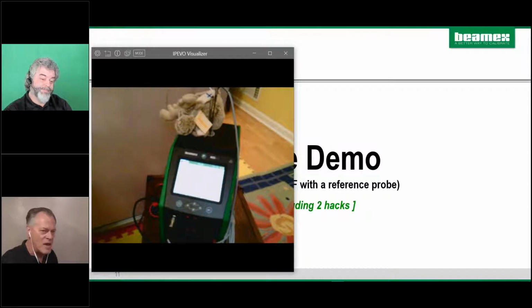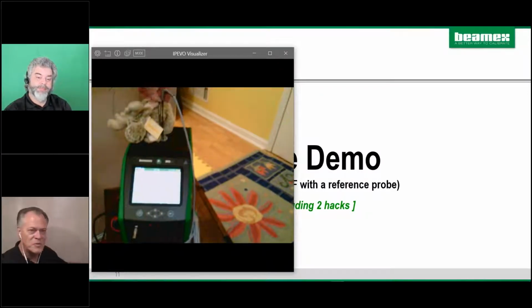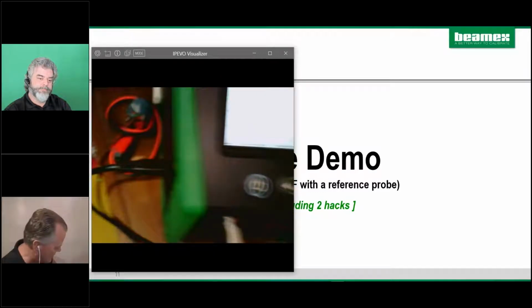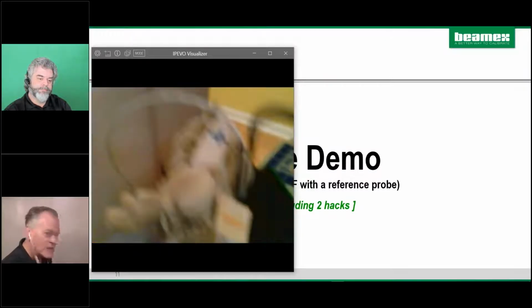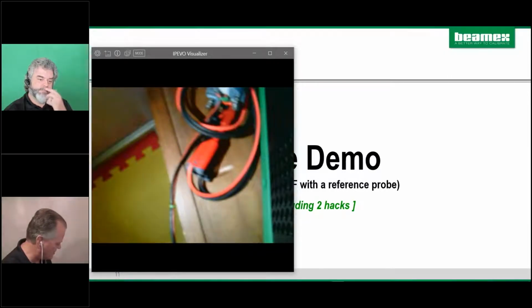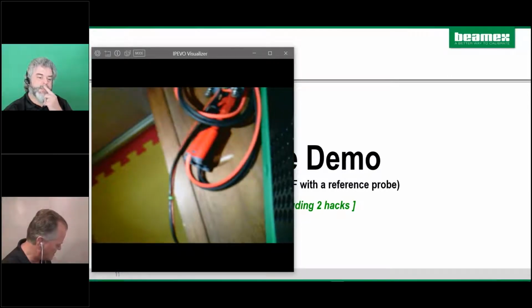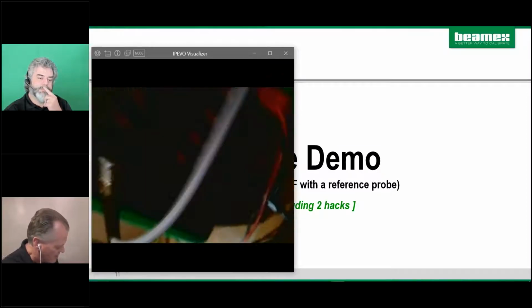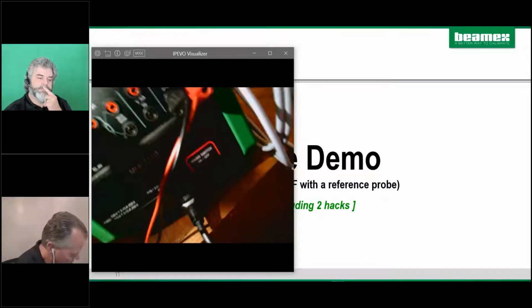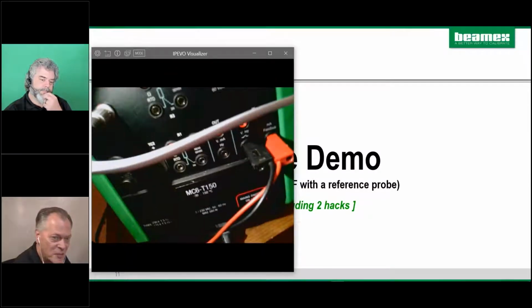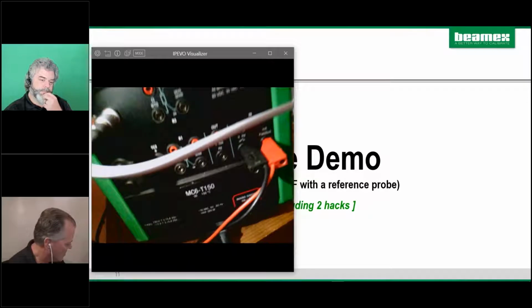But this is our dry block. I've got 2 temperature probes inserted in this block. Let me give you a little tour - I know it's a little out of focus, and I have a spotlight here. This RTD coming out is connected to this little transmitter down here, a 3-wire connection. The leads are coming out, and we're connecting to the milliamp meter built into the dry block. So we're measuring milliamps, and we're powering the transmitter.